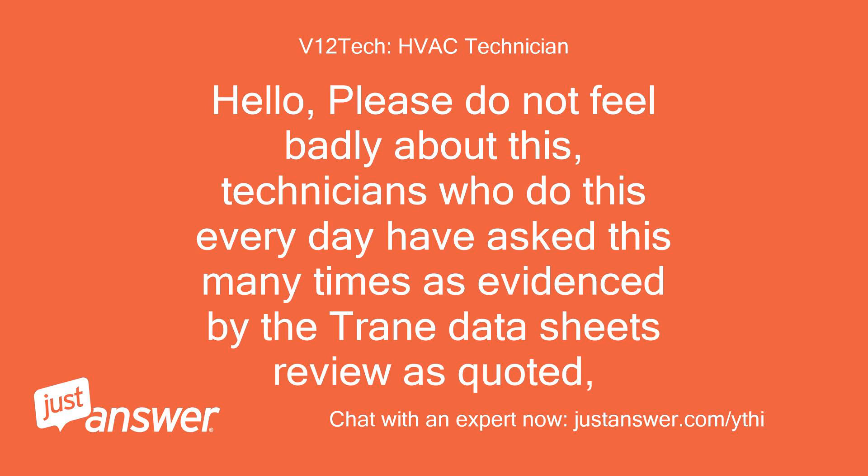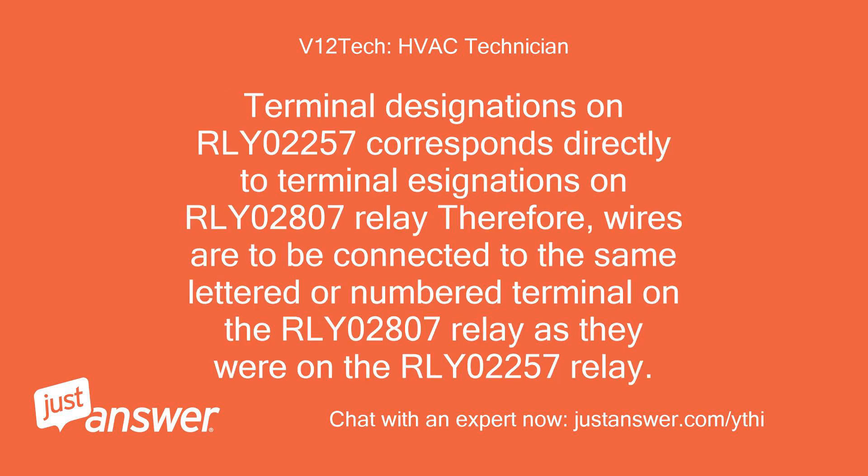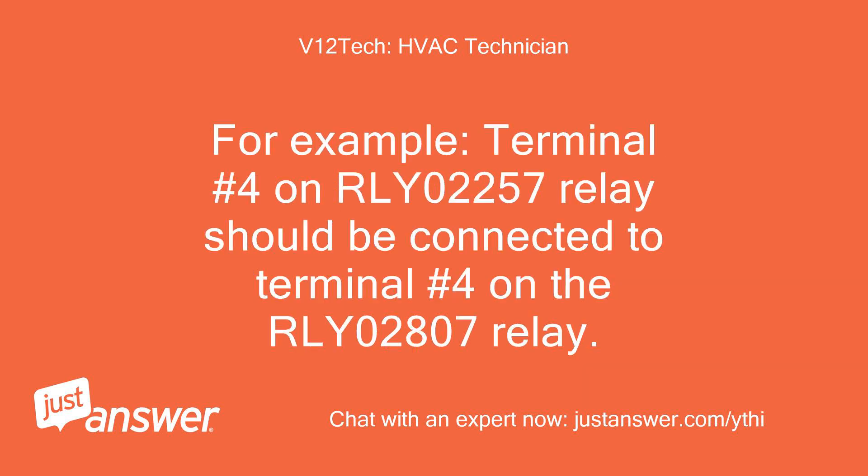Hello, please do not feel badly about this. Technicians who do this every day have asked this many times, as evidenced by the Trane data sheets review as quoted. Terminal designations on RLY 02257 correspond directly to terminal designations on RLY 02807 relay. Therefore, wires are to be connected to the same lettered or numbered terminal on the RLY 02807 relay as they were on the RLY 02257 relay. For example, terminal number 4 on RLY 02257 should be connected to terminal number 4 on the RLY 02807 relay.